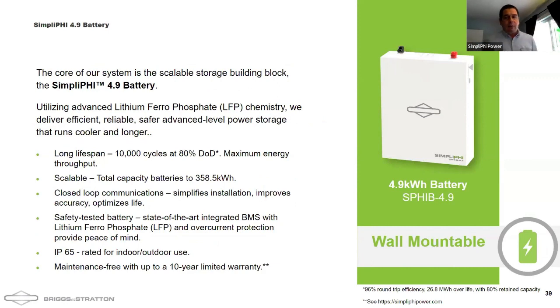The battery we're releasing with this is the 4.9 kilowatt hour. It's the same chemistry we've discussed, still has a breaker, still has that closed loop communication that makes the SimpliPHI battery so special, but it's a larger form factor. I've heard feedback about some AHJs having a ceiling of 20 kilowatt hours before installation becomes more problematic. This is a great product to drop four of these batteries in, stay under that 20 kilowatt hour ceiling, and simplify your permitting and installation process.